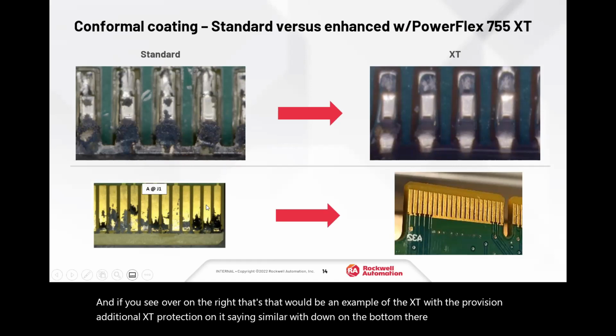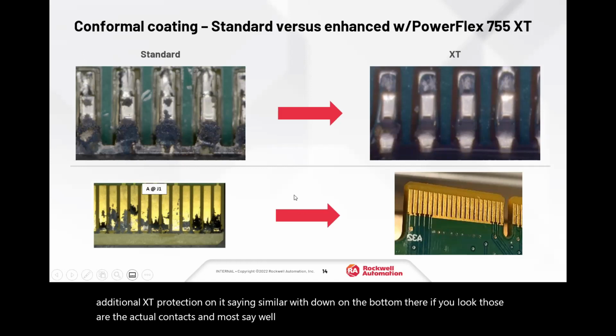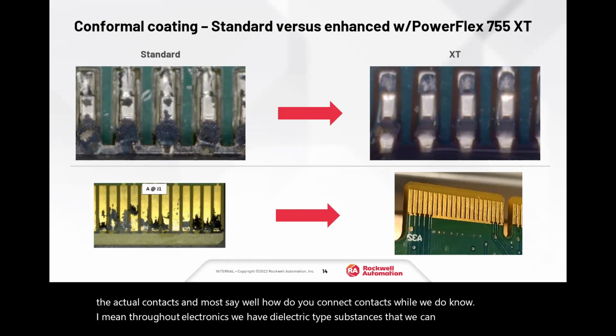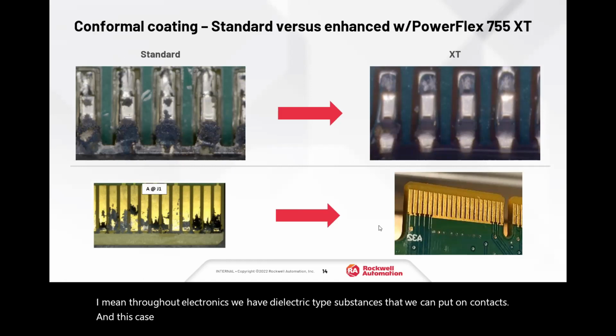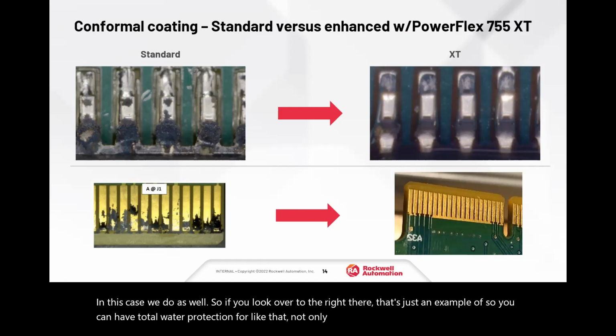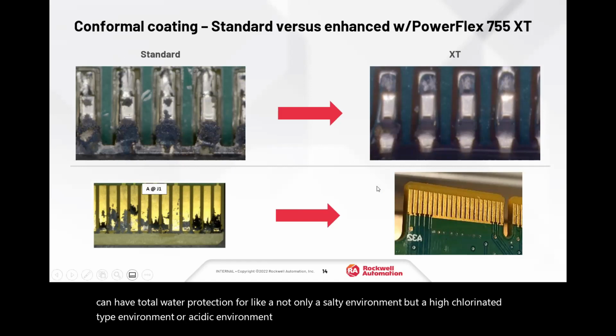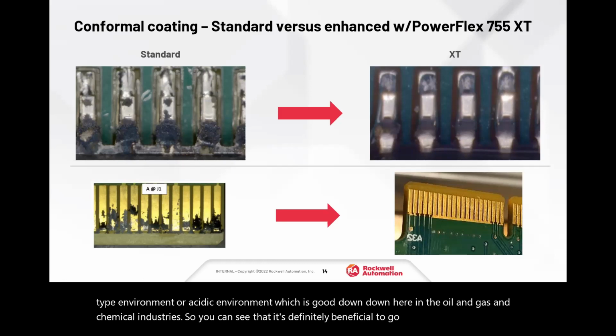If you look, those are the actual contacts, and most say, well, how do you protect contacts? Well, we do know, throughout electronics, we have dielectric type substances that we can put on contacts. In this case, we do as well. So if you look over to the right there, that's just an example, so you can have total protection for not only a salty environment, but a highly chlorinated or acidic environment, which is good down here in the oil and gas and chemical industries. So you can see that it's definitely beneficial to go with the XT option.